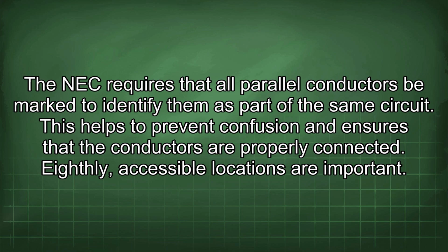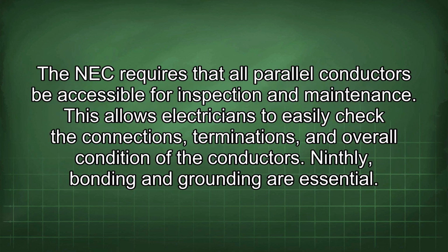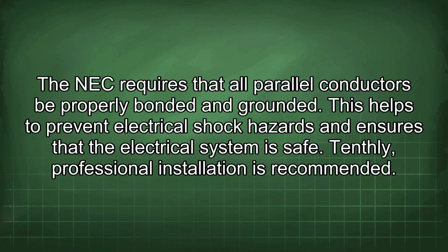Eighthly, accessible locations are important. The NEC requires that all parallel conductors be accessible for inspection and maintenance. This allows electricians to easily check the connections, terminations, and overall condition of the conductors. Ninthly, bonding and grounding are essential. The NEC requires that all parallel conductors be properly bonded and grounded. This helps to prevent electrical shock hazards and ensures that the electrical system is safe.